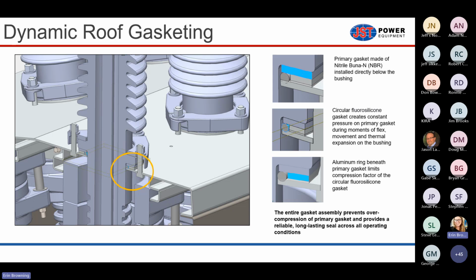I want to point out that this top blue gasket right here would be the gasket that comes with the bushing from the bushing manufacturer. And other OEMs, that's all they use is that top gasket. They gasket it, they bolt it down, and they're good to go. And then a couple years in service, that gasket starts to tear, and it leans and over compresses in certain spots, so you end up with small cracks and crevices where stuff can get into the high voltage cabinet.